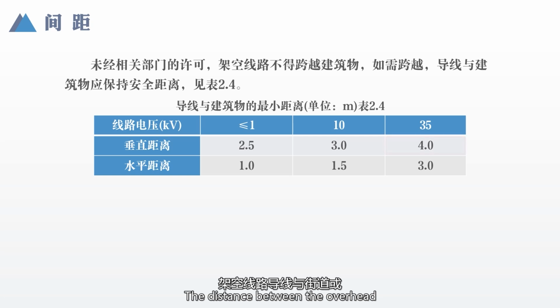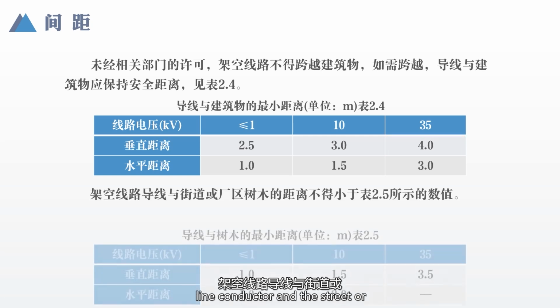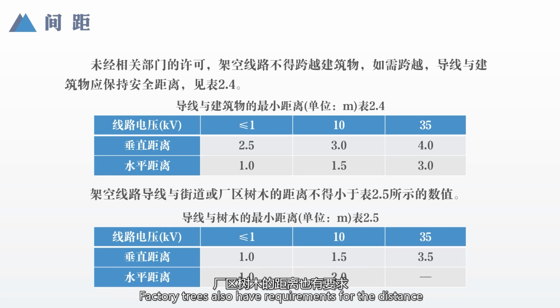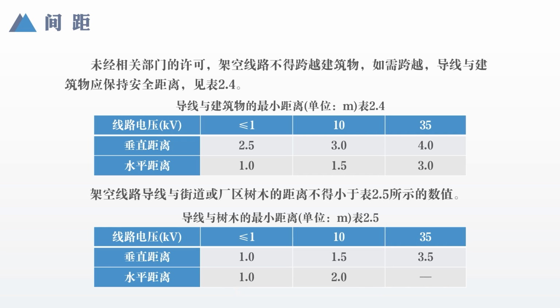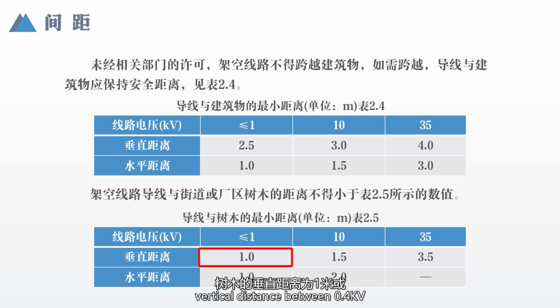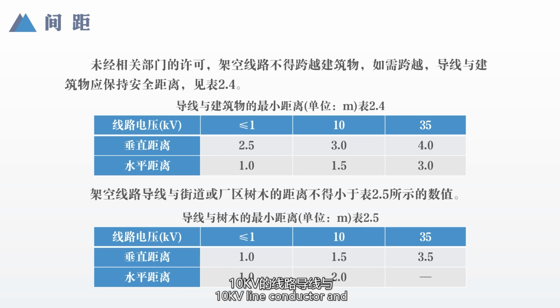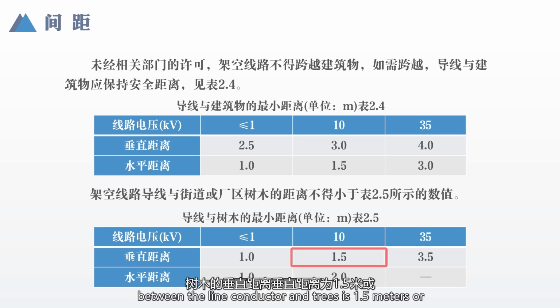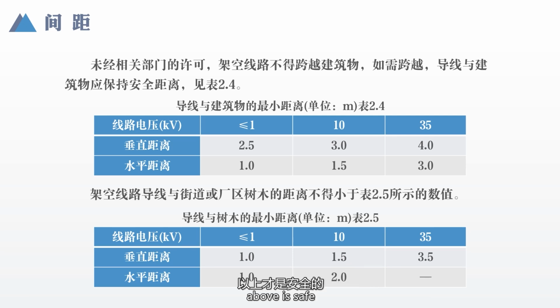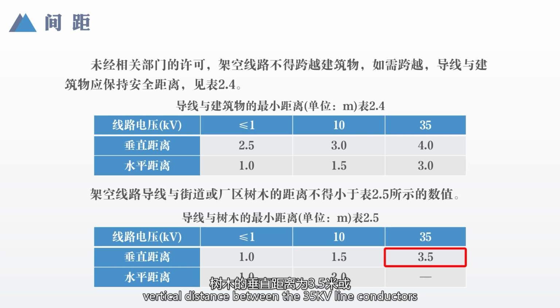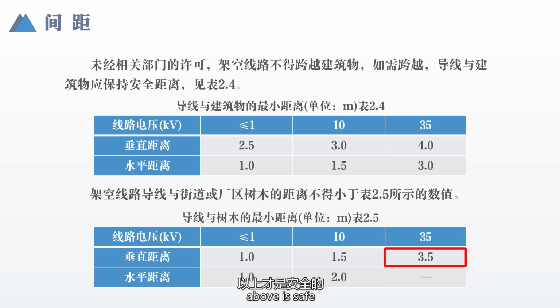The distance between the overhead line conductor and street or factory trees also has requirements. For a 0.4 kilovolt line, the vertical distance between the conductor and trees is 1 meter or above to be safe. For a 10 kV line, the vertical distance between the conductor and trees is 1.5 meters or above to be safe. For a 35 kV line, the vertical distance between the conductor and trees is 3.5 meters or above to be safe.